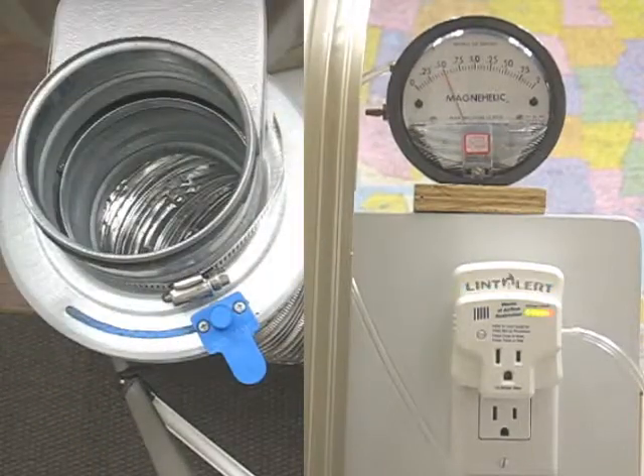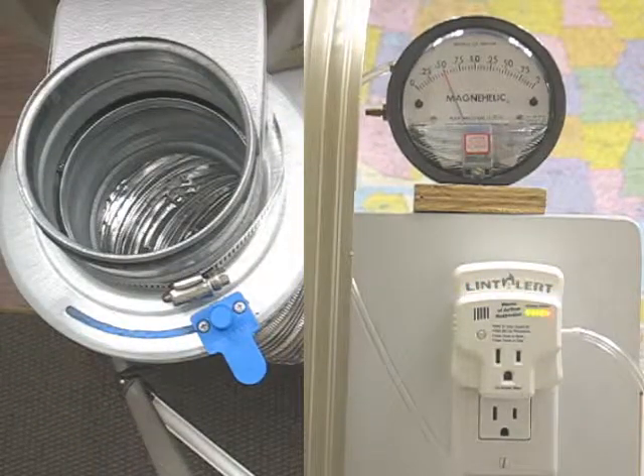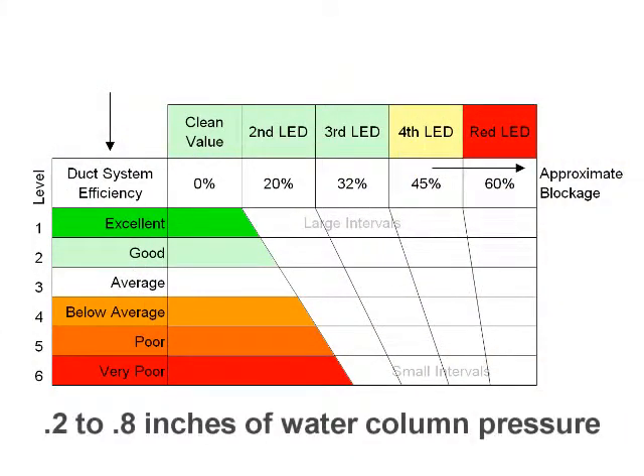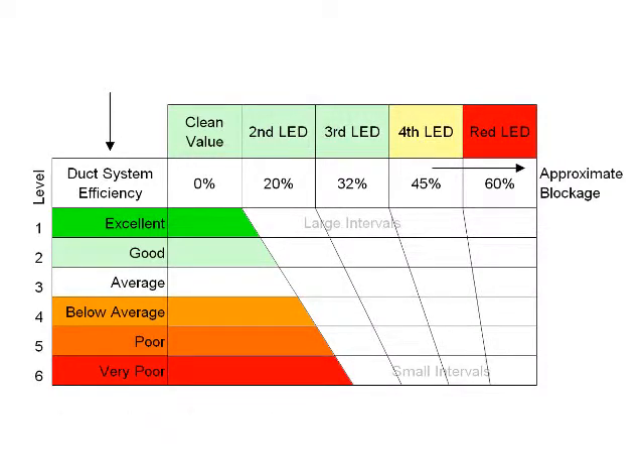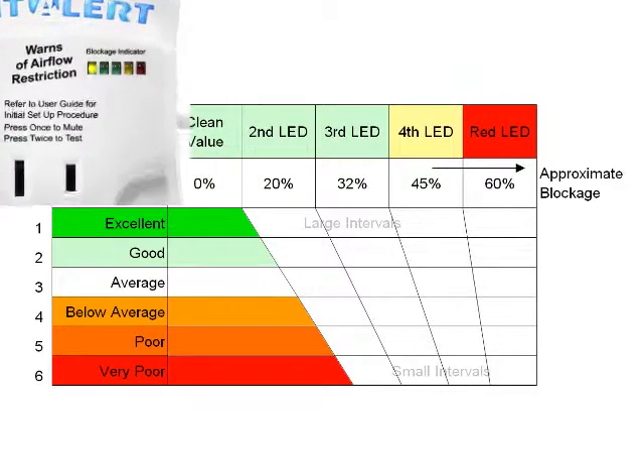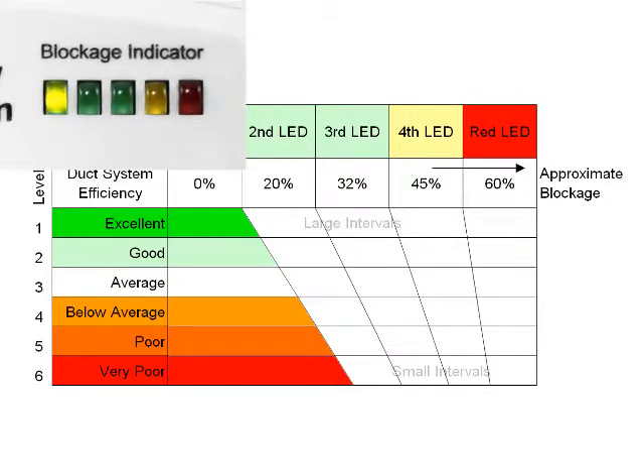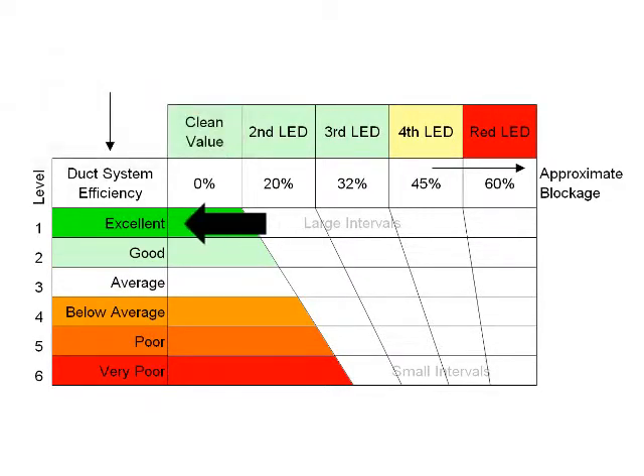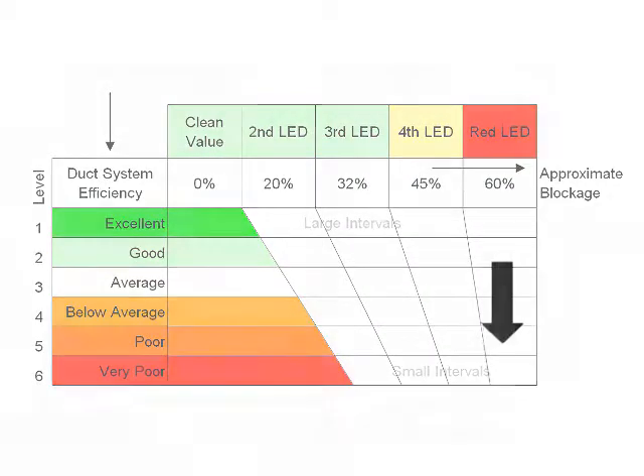In this final effort, we'll attempt a calibration with a typical or likely home environment. Pressure levels in this group range from 0.2 to 0.8 inches of water column pressure. Depending on what the LintAlert sensor finds will determine what pressure intervals the microprocessor will use to illuminate the LED blockage indicator lights. The lower the initial clean value pressure found, the larger the intervals, and on the flip side, the higher the initial clean value pressure found, the smaller the intervals.